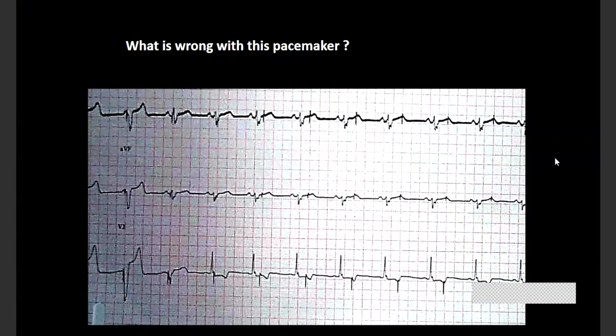The only spike which does not fall on the refractory period is captured here. Here you find that the spike is falling in the non-refractory period, when the ventricle is completely normal. At that point of time, if a spike falls, it is capturing. But if a spike falls during the refractory period, it is not going to capture at all. So this is why this is happening, because this is not sensing the ventricle. What you realize is the output is normal, the lead is normal, the capture is normal. Then the problem is it is not sensing an intrinsic activation.